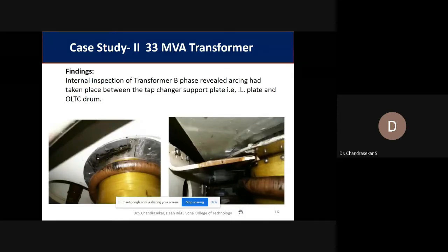So that blackish portion clearly shows that continuous arcing happened. If this arcing continues for a long duration, and if someone is not attending to this problem, then what will happen? After a long time, one day, it will lead to complete failure of the system.